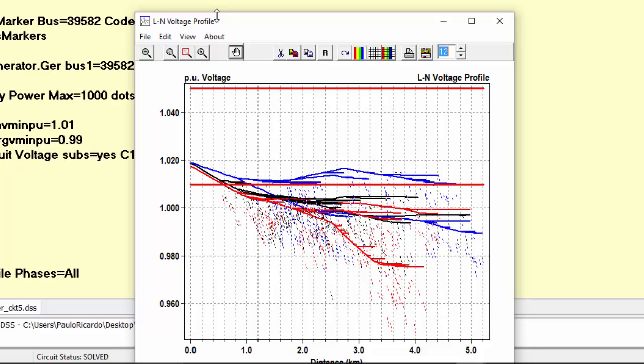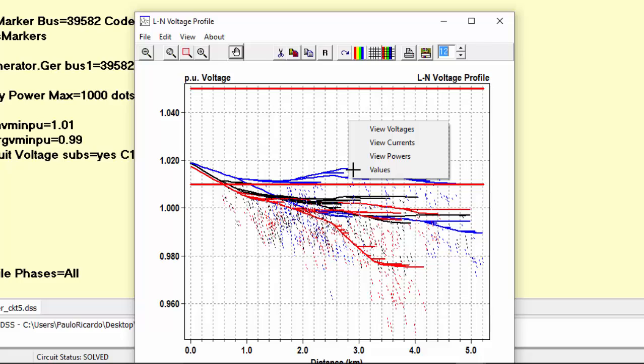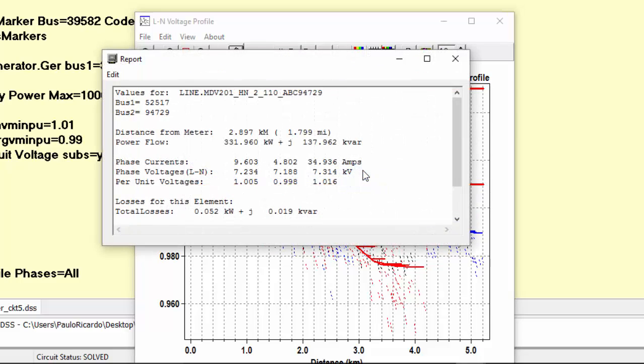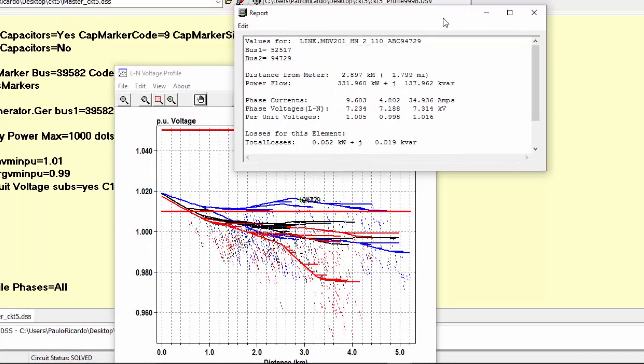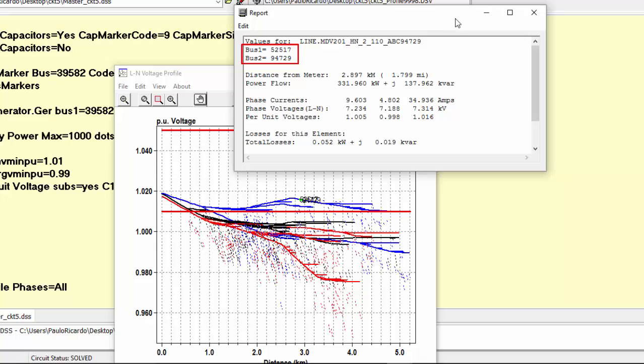Each of these profiles represent a phase of the system. The black one represents the nodal voltage of phase 1. The red represents the nodal voltage of phase 2. And the blue line represents the nodal voltage of phase 3. The full profiles represent 3 phase lines and the dashed lines represent single phase lines. Let's take, for example, this line here. Like in the circuit plot, we can right click on this plot and get some results for this line. So, the name of this line is this. It is connected to buses 52517 and 94729. And its per unit voltage are 1.005, 0.998 and 1.016.